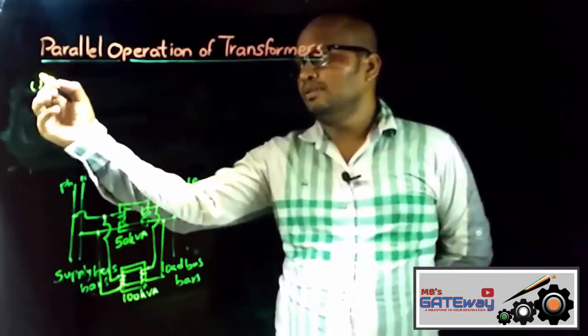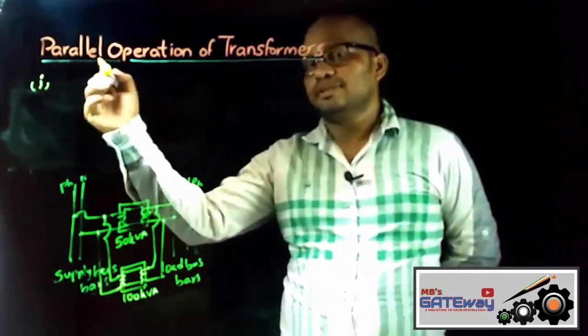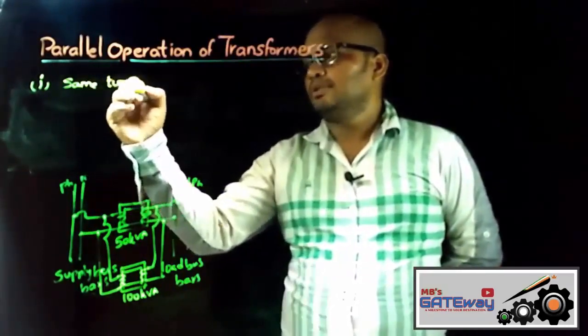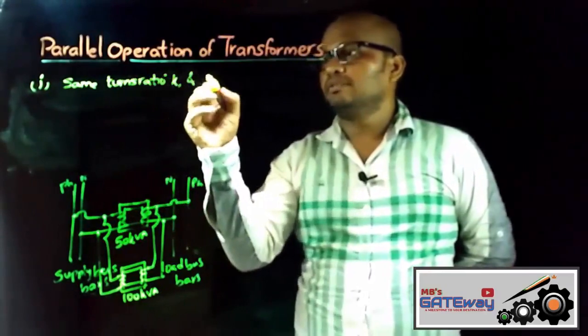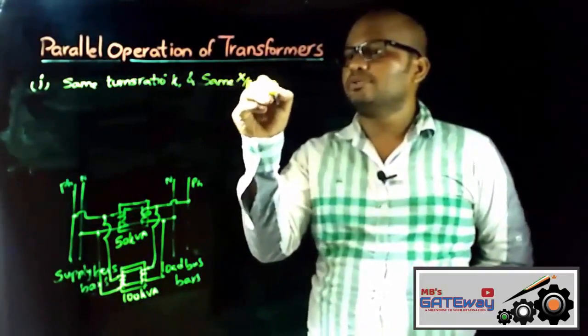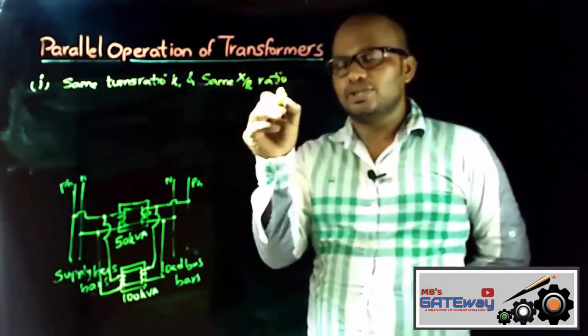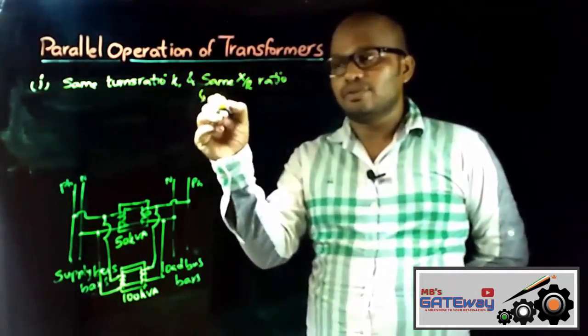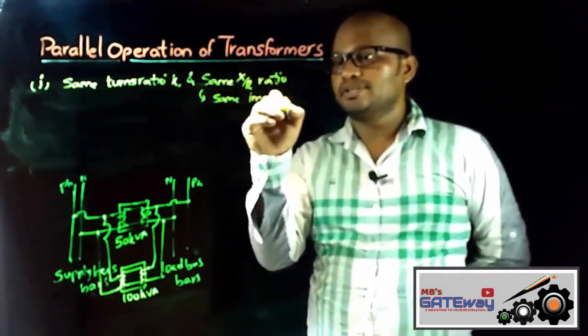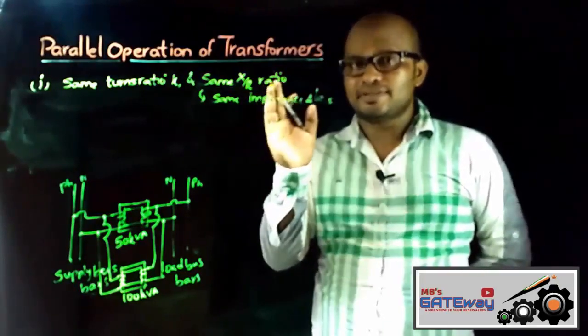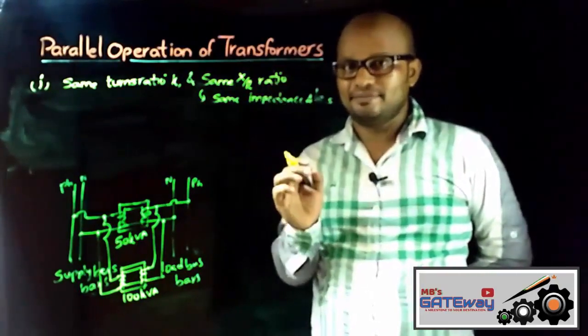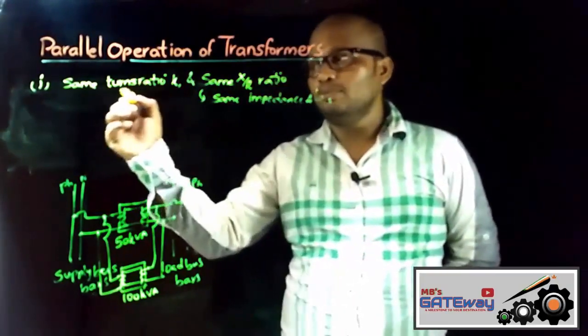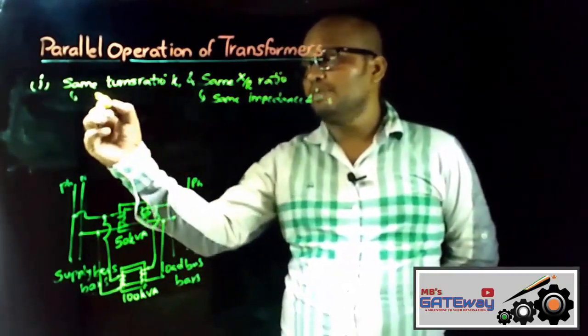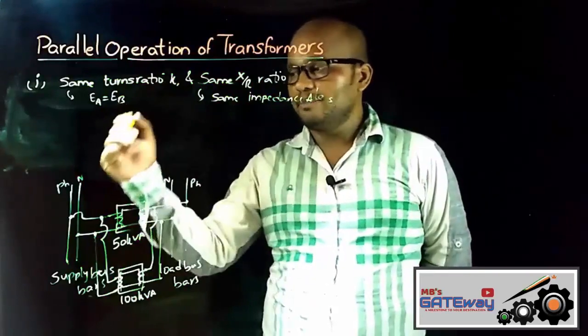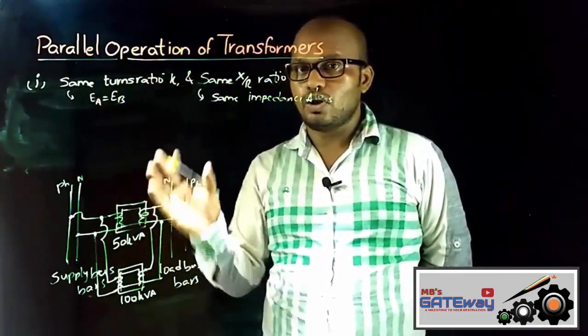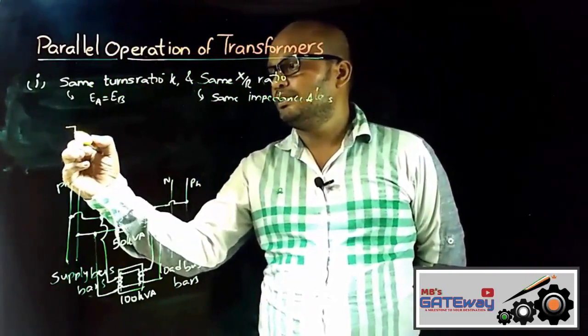And here there are three cases that we must study, that is, transformers having the same turns ratio and the same X by R ratio. Here the same X by R ratio means the transformers have the same impedance triangles, that is, impedance triangles of the same shape and size. And the same turns ratio means the secondary induced EMFs are the same. And the schematic diagram of two transformers operating in parallel can be drawn like this.